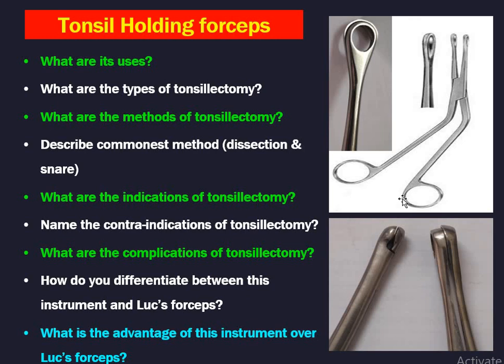The differentiation between tonsil holding forceps and Luc's forceps is that in Luc's forceps the two blades directly fit each other. But in tonsil holding forceps, as you can see here, the lower lip is bigger than the upper lip so there will be no crossing and cutting of the tonsils during holding. So tonsils can be held without trauma. In Luc's forceps there will be trauma and the tonsils will be torn or detached from the side when grasped.